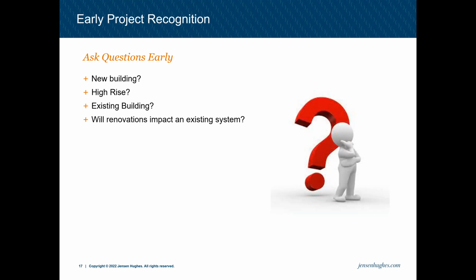So, early project recognition: we want to ask as many questions early in terms of smoke control. If it's a new building, it can be pretty self-explanatory. We consult with our code consultant. For new buildings, if it's a high-rise building, we should be able to identify pretty quickly that a smoke control system, a stair pressurization system, is going to be needed. If we ask the questions early, do we want to have elevator lobbies? And if not, if we want that open floor plan, then we can incorporate the elevator pressurization quickly. Do we have an atrium that connects three or more stories? Are we working at a prison? Those items, when it's a new building, we can identify pretty early.